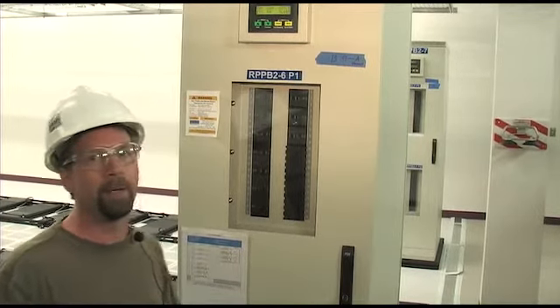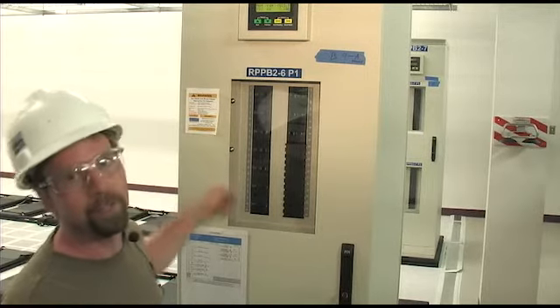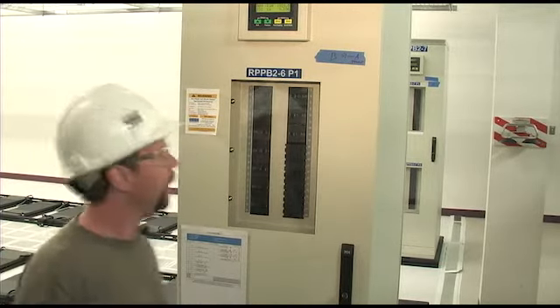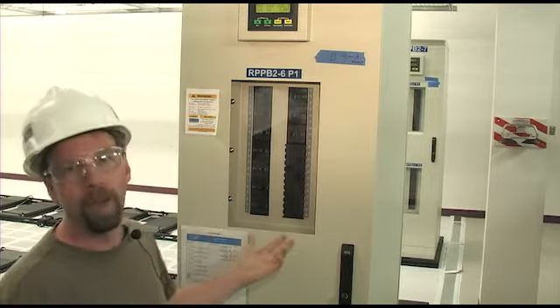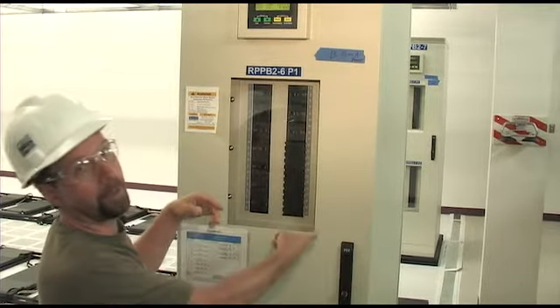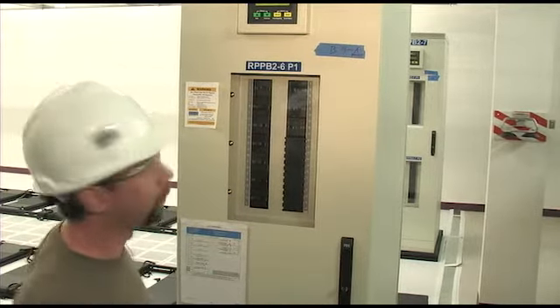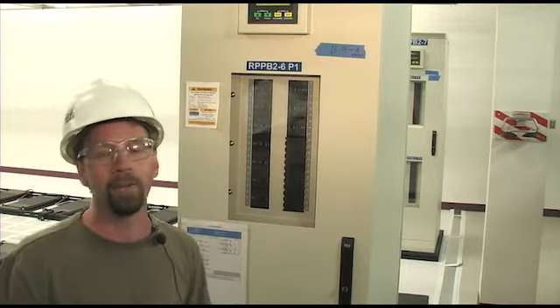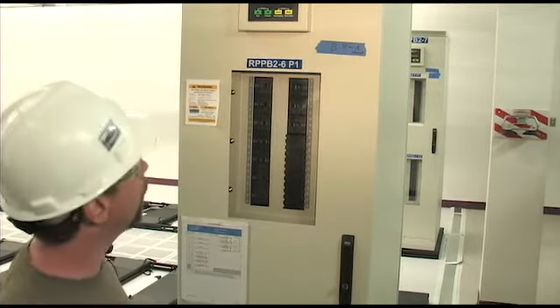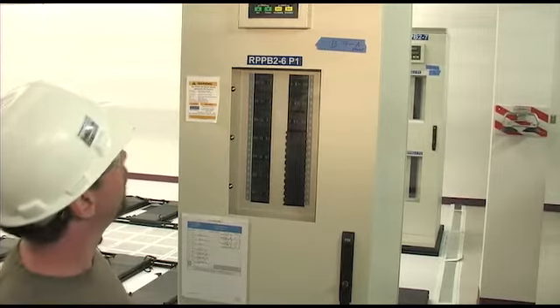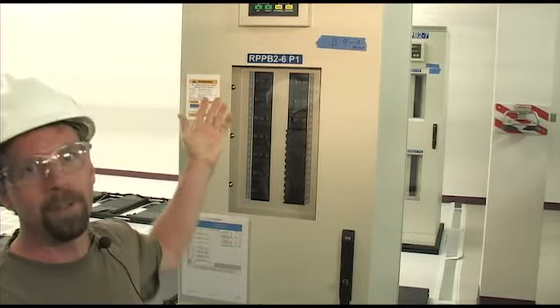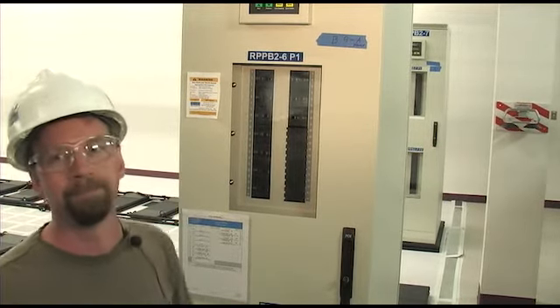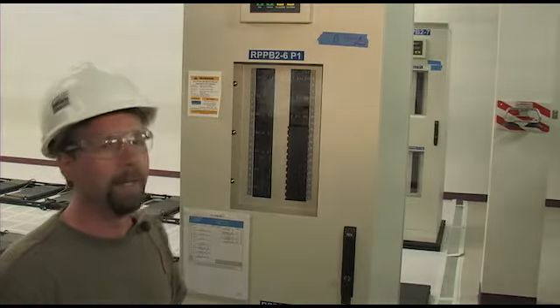Periodically, when you have somebody come in and scan your breakers to see if anything is toasty, anything is hot, and from there you can diagnose whether you can take the panel board off and check for currents to see if there's something that actually is a loose connection or you got too much current. And that's pretty much all you really need to do is check for heating, and then just check your voltages and currents. Just check a few of them to see if they're accurate, and they may need to be calibrated. And that's it.